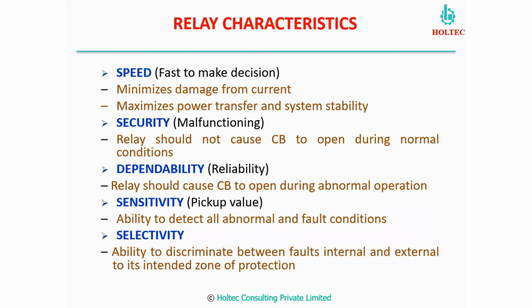Now coming to the relay characteristics. What are the characteristics which we have to have in the relay to operate, which will make it very reliable and sensible? The first but very important is the speed. It should have a speed to make very fast decisions. If it makes very fast decisions, the damage due to the fault current will be minimized. As soon as the fault is analyzed and the tripping is initiated, the damage due to the fault current will be minimized. Not only minimized, we can also ensure the system stability. This system stability we will discuss in detail further.